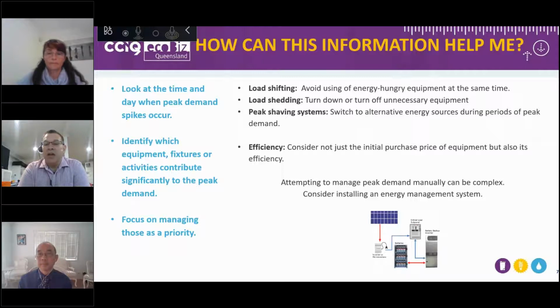These peak shaving systems actively monitor the demand for a particular site at any particular time of day, and can work to parameters that are uploaded to the management system. Of course, the last and the classic way of helping your peak demand is efficiency. We've all seen the efficiency drives of changing out light bulbs and high bays from the old metal halide fittings to the more modern LED fittings. But efficiency is an ongoing project. I've seen lights that were top of the line 3 or 4 years ago can now be replaced with even more efficient equipment and still have really good paybacks for particular customers. So these are the 4 key ways that you can help reduce your peak demand.